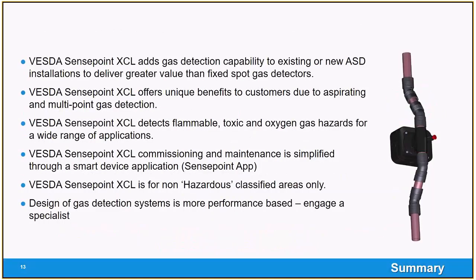In conclusion, VESDA Sensepoint XCL adds gas detection capability to existing or new ASD pipe network installations to deliver greater value than fixed spot gas detectors. VESDA Sensepoint XCL offers unique benefits to customers due to its aspirating and multi-point gas detection methodology. VESDA Sensepoint XCL detects flammable, toxic, and oxygen gas hazards for a wide range of applications. The detector can be quickly and easily commissioned and maintained through your smart device using an app called Sensepoint app. VESDA Sensepoint XCL is for non-hazardous classified areas only.